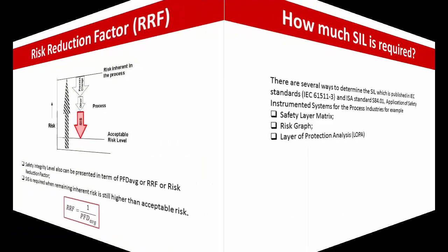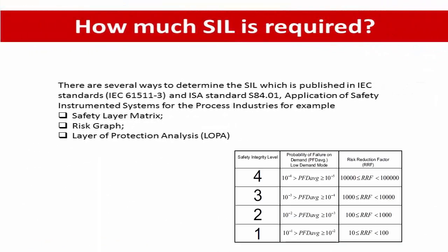How much SIL is required? As per the picture above, SIL levels are linked from one to four depending on probability of failure on demand and risk reduction factor. There are several ways to determine the SIL level, which are published by IEC 61511 and ISA S84.01, the standard for application of safety instrumented systems in the process industry. Example methodologies include the safety layer matrix, risk graph, or layer of protection analysis, or LOPA. The next video will explain how to determine the SIL level. Thank you for watching.